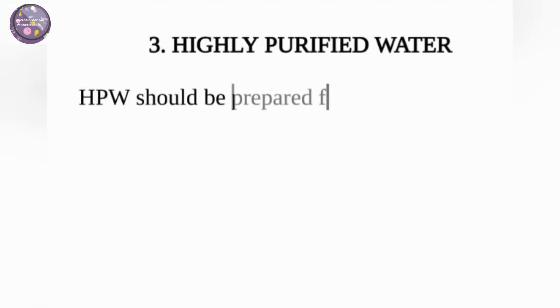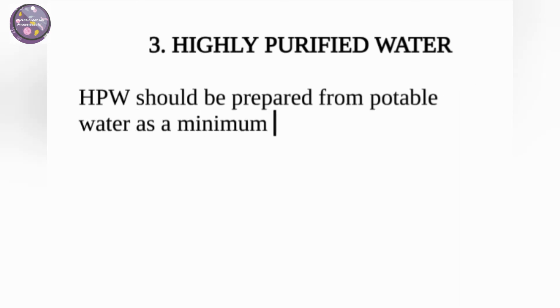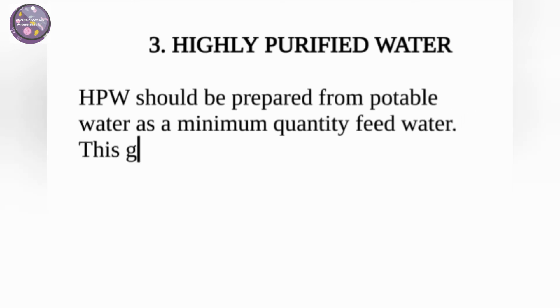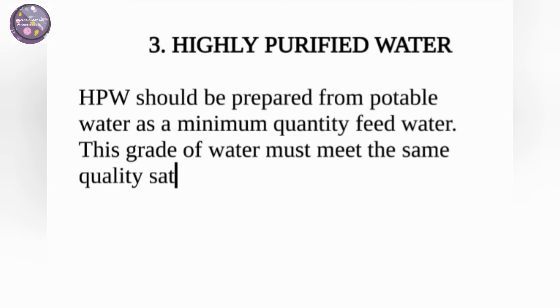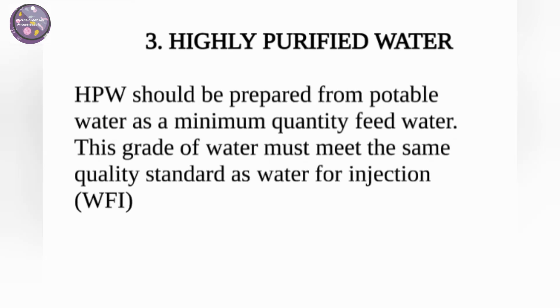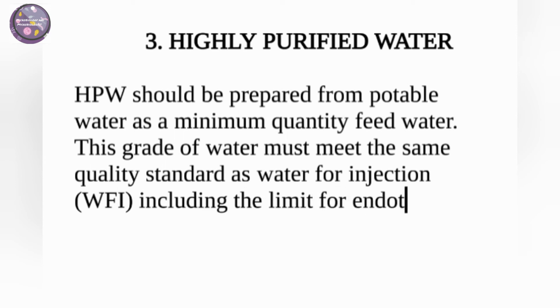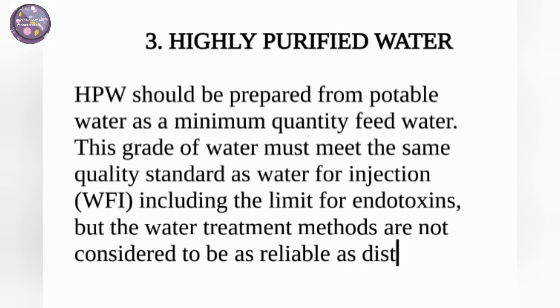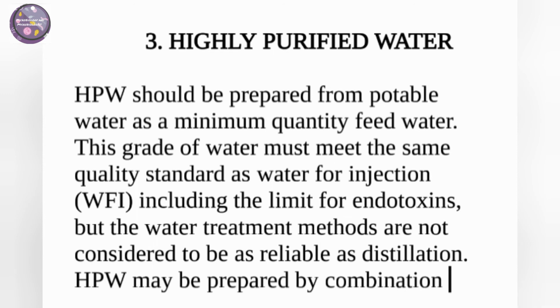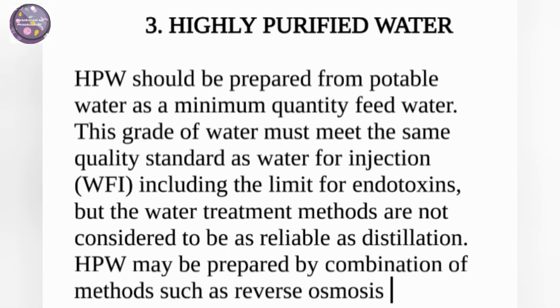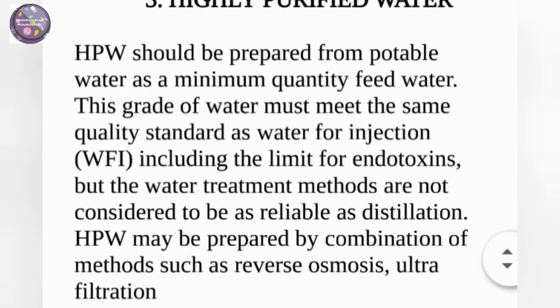Highly purified water should be prepared from potable water as a minimum quality feed water. This grade of water must meet the same quality standard as water for injection, including the limit for endotoxins, but the water treatment methods are not considered to be as reliable as distillation. Highly purified water may be prepared by combinations of methods such as reverse osmosis, ultrafiltration, and deionization.